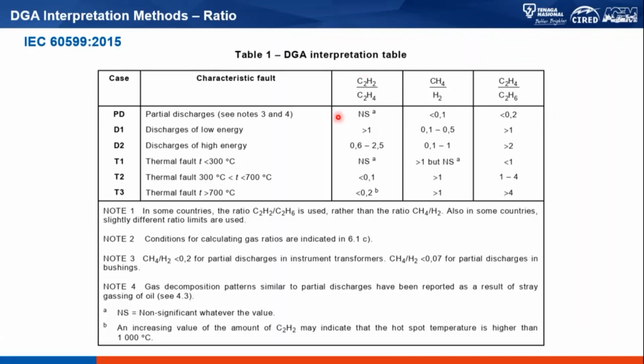This technique is based on three main ratios used as an indication whenever a pattern exists to show whether or not there is partial discharge happening, discharge of low energy, discharge of high energy, thermal fault of lower degree, middle degree, or the highest degree of more than 700 degrees. Whenever all these ratios indicate a positive sign for any individual gas, normally what we get is one type of fault that satisfies all at the same time.